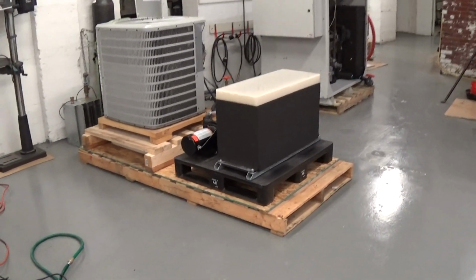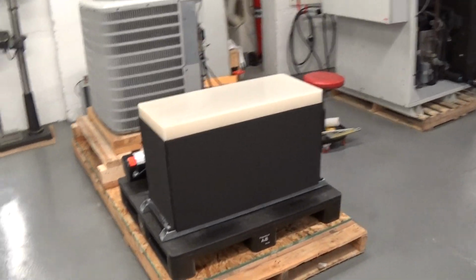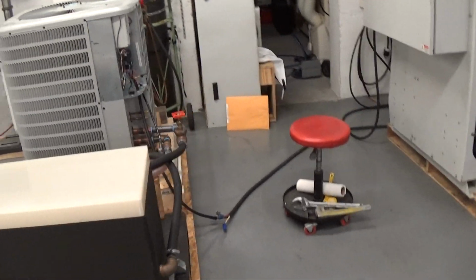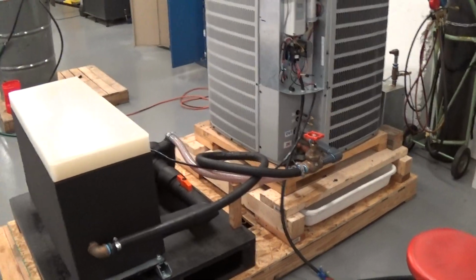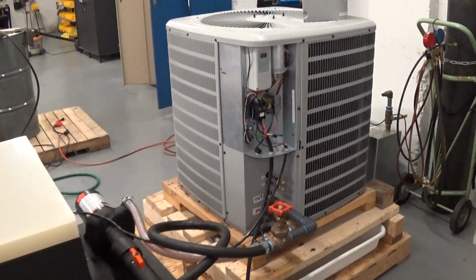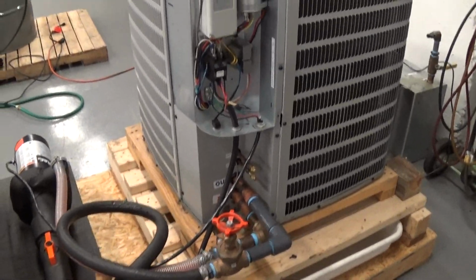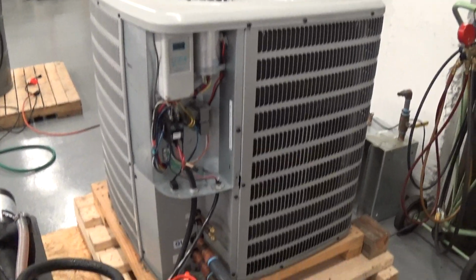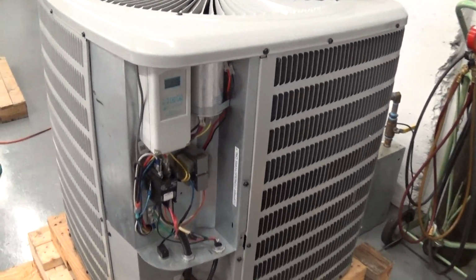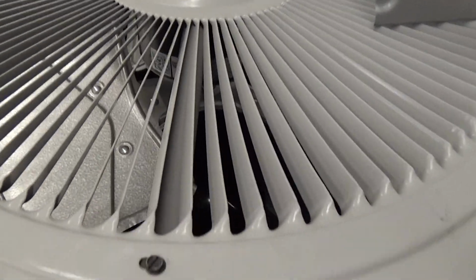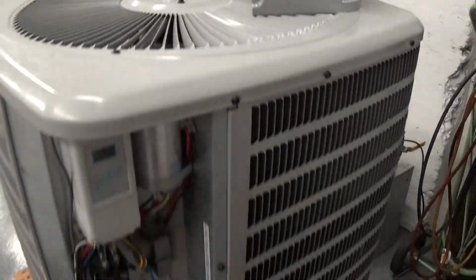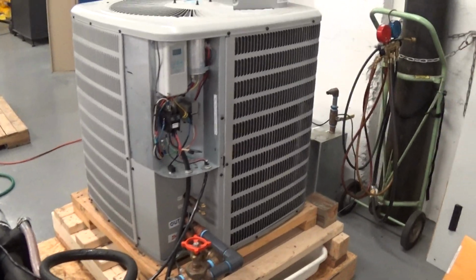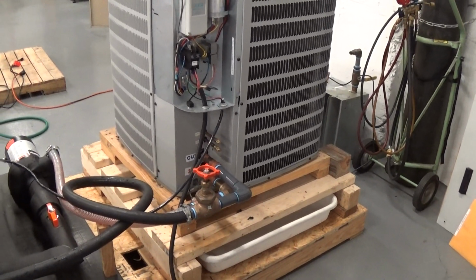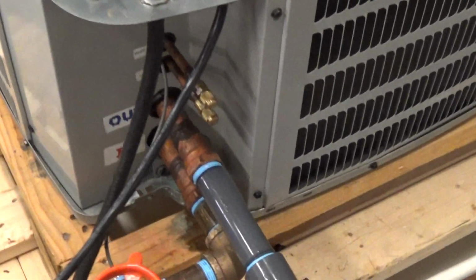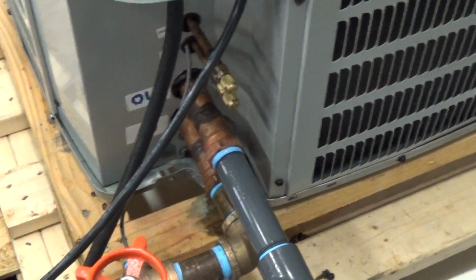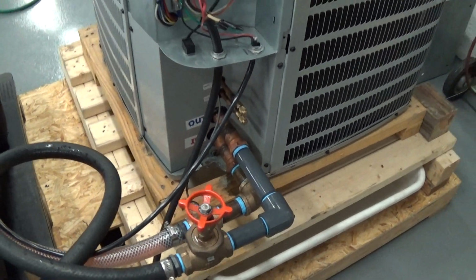We're going to do a runoff video or videos of this 3 horsepower glycol system intended for and set up for a brewery. In this case, this is one of our 3 horsepower Heatseeker modules, is what we call that. And this is kind of interesting in that it's a condenser compressor arrangement, but actually inside here is where we have a plate heat exchanger, a flow switch, an adjustable refrigerant pressure switch, and so forth. And then down below here we have the inlet and outlet connections, which are 1 inch, to go out to your process or processes.